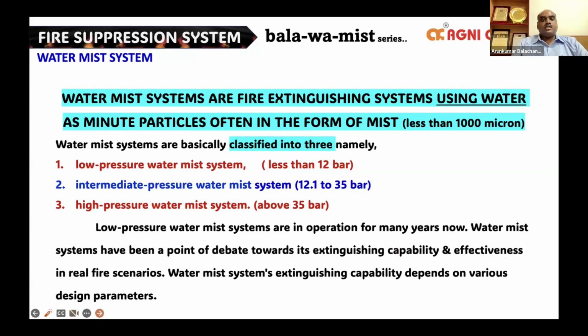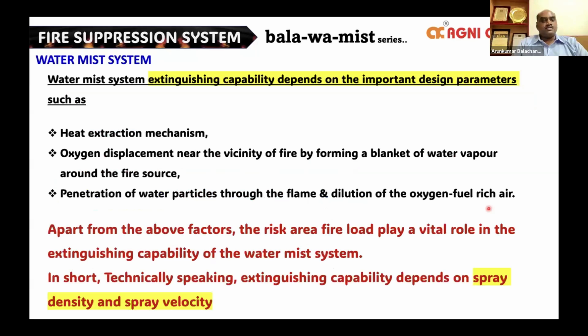But this extinguishing capability will depend on three important design parameters. One is the heat extraction mechanism, which is nothing but the cooling effect. Second is oxygen displacement near the vicinity of fire by forming a blanket of water vapor around the fire source. As I said earlier, for breaking the fire, we need to remove heat as well as remove the oxygen content. So in water mist, we are trying to have a cooling effect using the heat extraction mechanism, and also we are trying to reduce the oxygen from feeding into the fire by creating a blanket of water vapor around the fire. Third, penetration of water particles through the flame and dilution of oxygen fuel rich air. So these are the parameters on which the extinguishing capability of a water mist system highly depends.